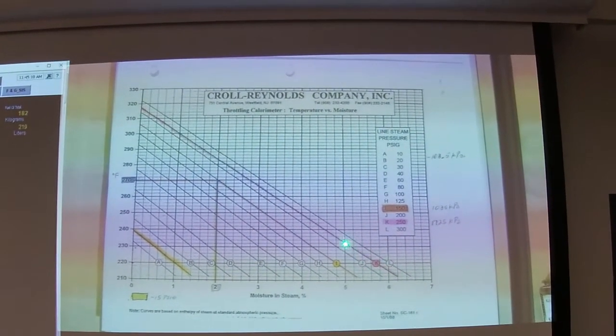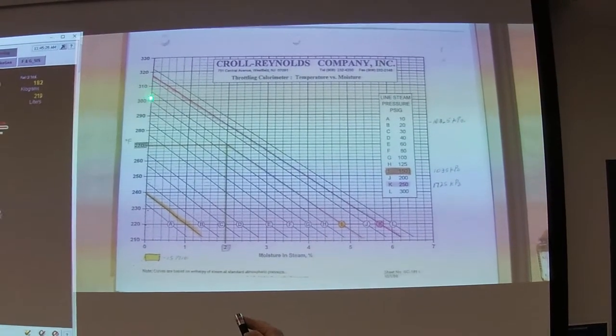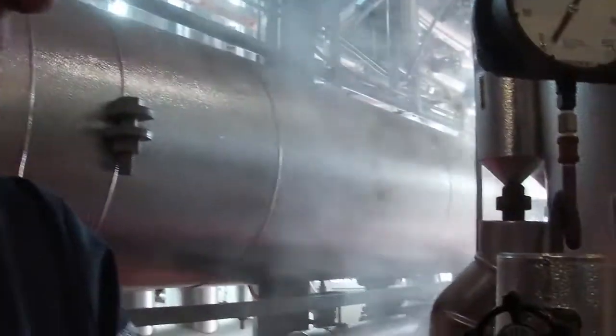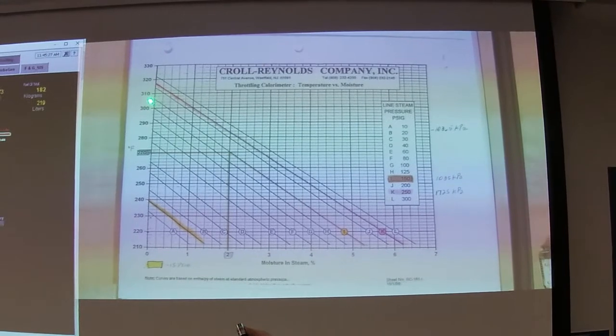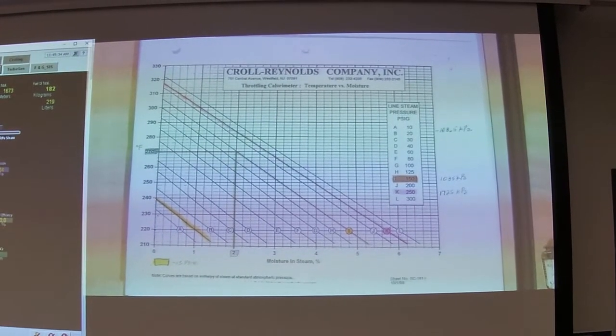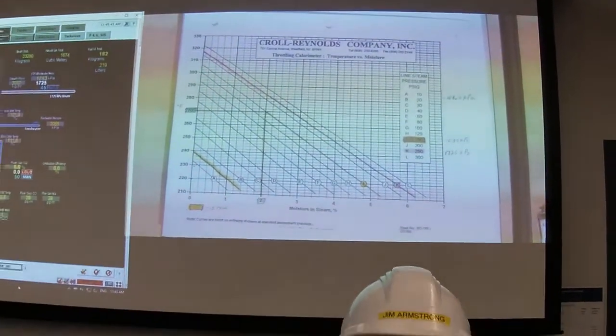This graph sitting on here is on our 1725 line — it's line K which comes up through here. We look at the temperature, and when we did it, it came in at 305 degrees Fahrenheit, which drops down to around 0.6 to 0.7% moisture content in the steam, which means that the boiler is running exactly where it's supposed to be running.